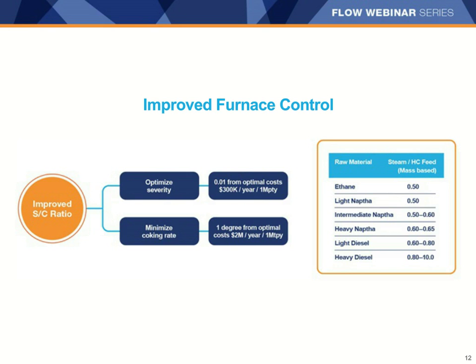Similarly, if you want to reduce the coking rate, the coil outlet temperature has to be carefully controlled. A deviation of just one degree away from the optimal temperature can cost up to $2 million per year per million ton per year capacity. Accurate measurement of the hydrocarbon feed is required to make sure you have the appropriate steam to hydrocarbon ratio and to maintain tight control of the ratio to improve the throughput and yield of the furnace.